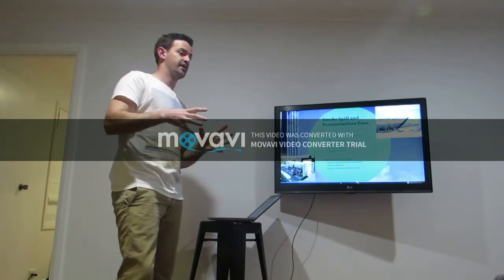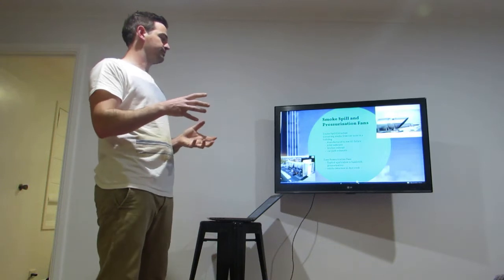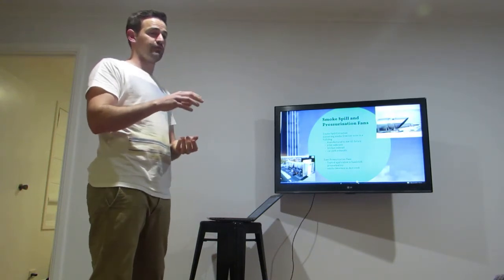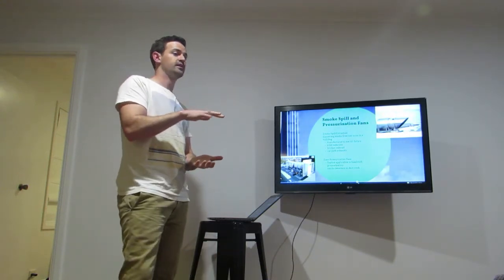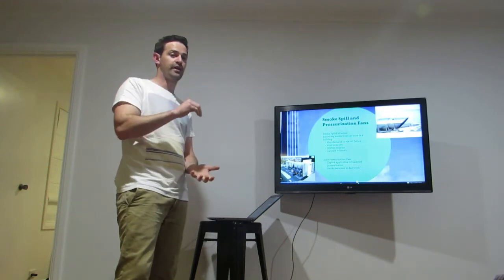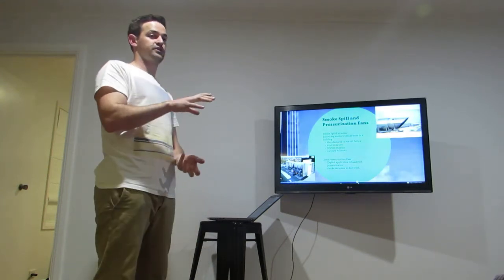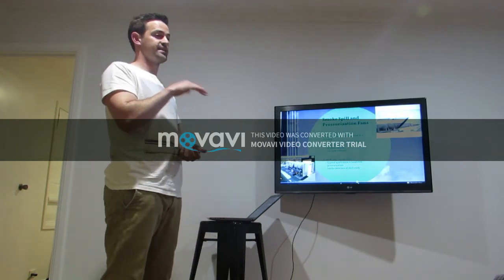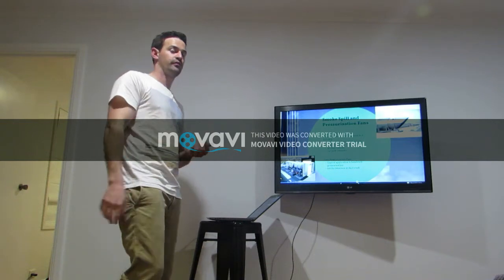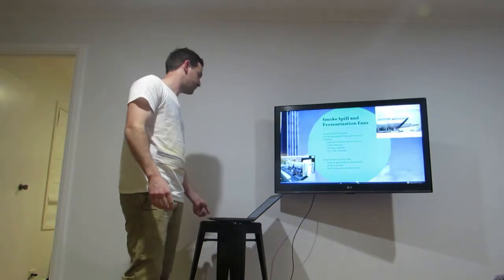We have zone pressurisation fans bringing in outside air. Now, pressurisation in a building, typically for multi-storey, is a sandwich effect. So we pressurise a floor above and below the fire floor, and this stops the smoke spreading to the other floors. On the floor that has the fire alarm, we open the spill dampers and extract the smoke from that level.